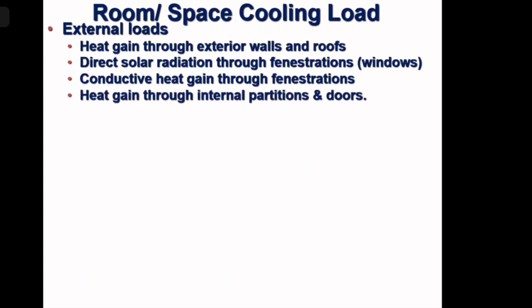Next. Heat gain through internal partitions or doors. Internal partitions and doors means the partition walls and doors which separate the air-conditioned room from an adjacent non-AC room. If the adjacent room is also AC, and both are running together, then on either side of the partition wall the temperature is the same, so there will not be any heat transfer. But if the partition wall segregates your air-conditioned room from a non-AC room, then heat will come through that. Next.